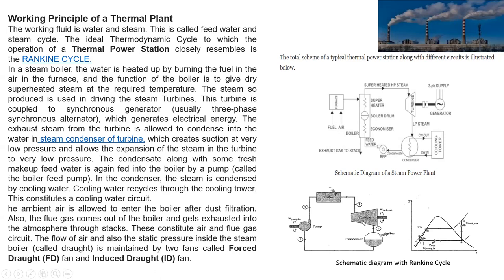The four main components of the thermal power plant are the turbine, boiler, pump, and condenser. The boiler converts water into steam with the help of burning coal. That steam is utilized to convert heat energy into mechanical energy by rotation of the turbine blades. The mechanical energy is then converted into electrical energy by the generator. The condenser condensates the exhaust steam from the turbine, and that condensate or feed water is pumped back to the boiler.